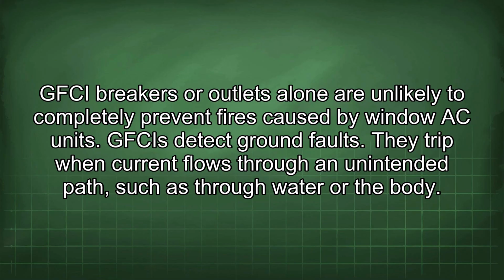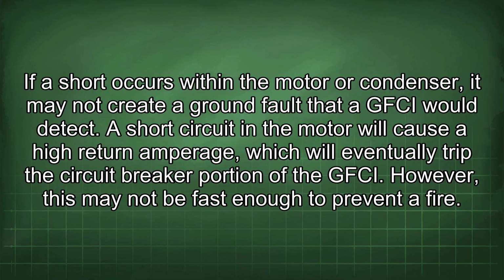GFCI breakers or outlets alone are unlikely to completely prevent fires caused by window AC units. GFCIs detect ground faults. They trip when current flows through an unintended path, such as through water or the body. If a short occurs within the motor or condenser, it may not create a ground fault that a GFCI would detect. A short circuit in the motor will cause a high return amperage, which will eventually trip the circuit breaker portion of the GFCI. However, this may not be fast enough to prevent a fire.